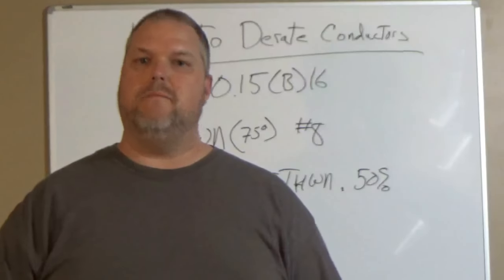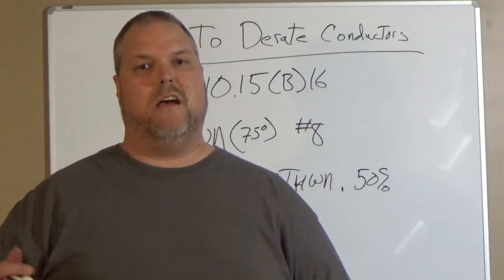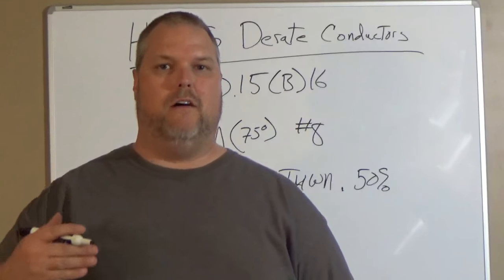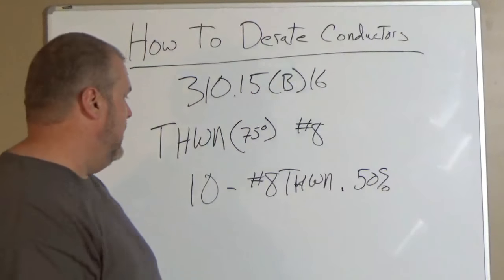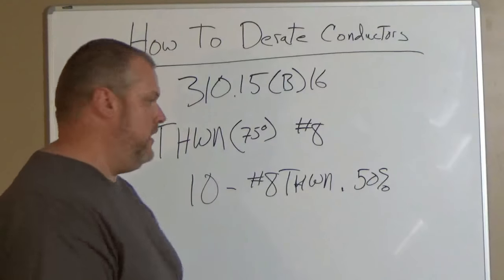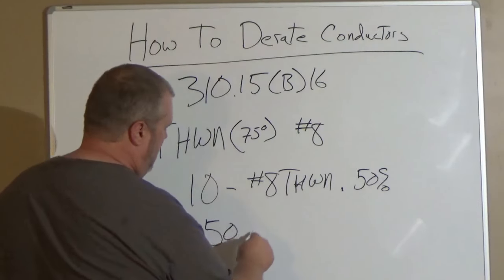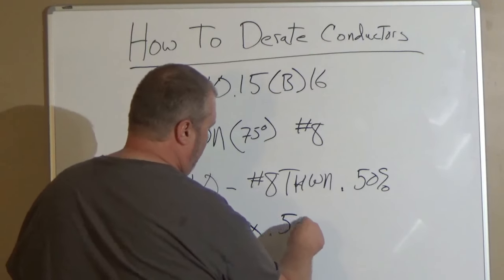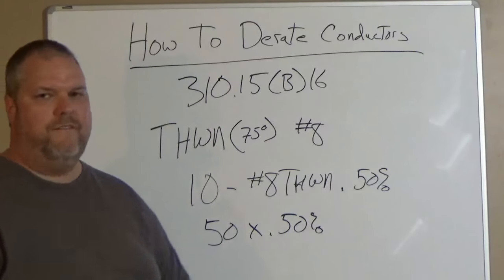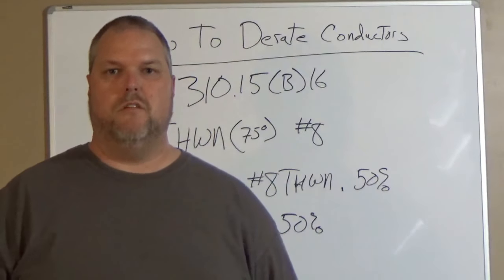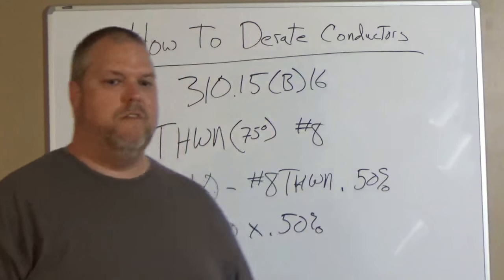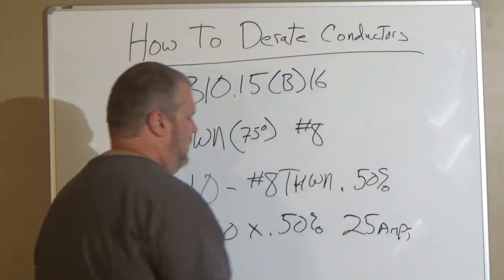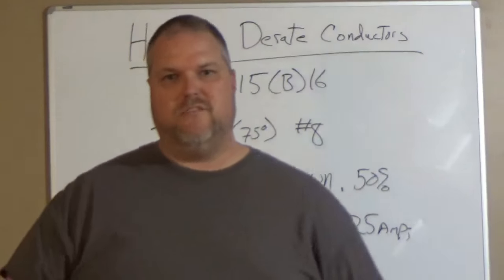Now I have to do the same thing I did for 80 percent, but because I went from four conductors to 10 conductors, that 80 percent now dropped to 50 percent. So I still take my 50, I multiply it by 0.50, and 50 times 0.50 now gives me 25 amps—it's 50 percent of it.